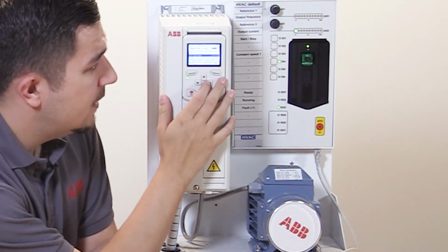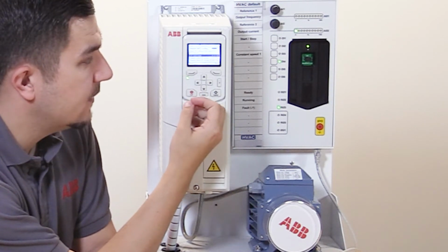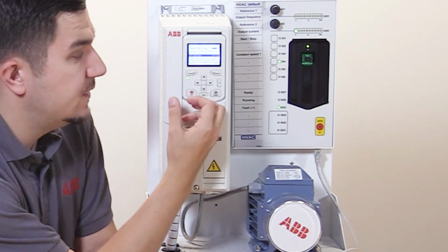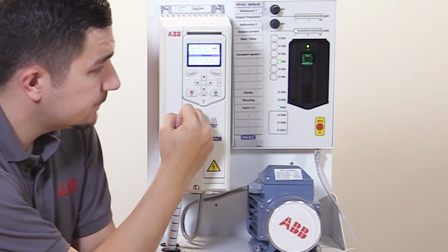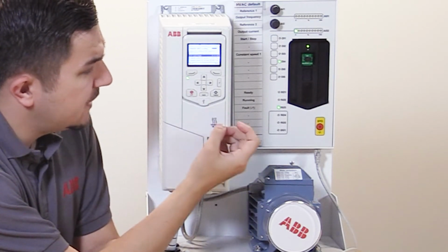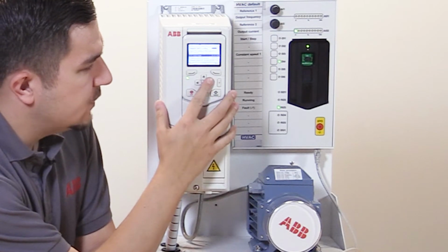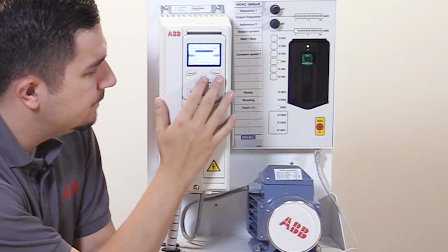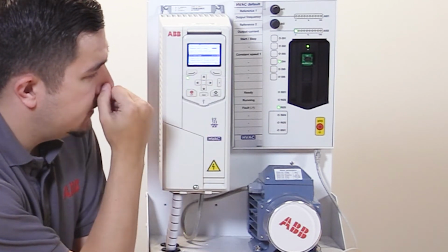And then we now set the settings for our set point 1 scaling, because we could be using a potentiometer to do this, and we've got a potentiometer on the actual control panel itself. So again, we've got to set the input range. I've got this set as 0 to 10 volts, but we can change that accordingly if we want to, and save that. And then we can do very similar with analog input 2.